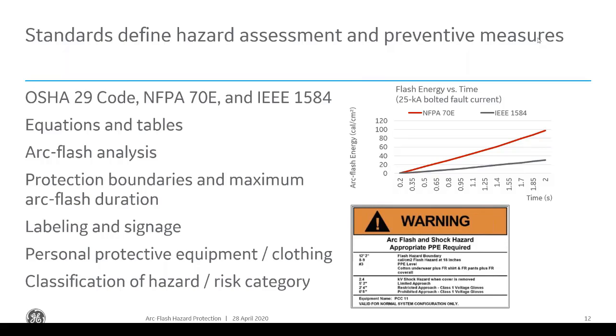There are standards out there, OSHA, NFPA, IEEE, and NEC, that talk about what you need to do to provide these mitigation techniques. One of the basic things is you need to know what kind of arc flash incident energy you have. So you need to do an arc flash analysis to determine your arc flash energy, because you don't know what type of signage to put, what type of boundaries to create, or what type of PPE to wear unless you actually know the arc flash energy that you're going to be exposed to.